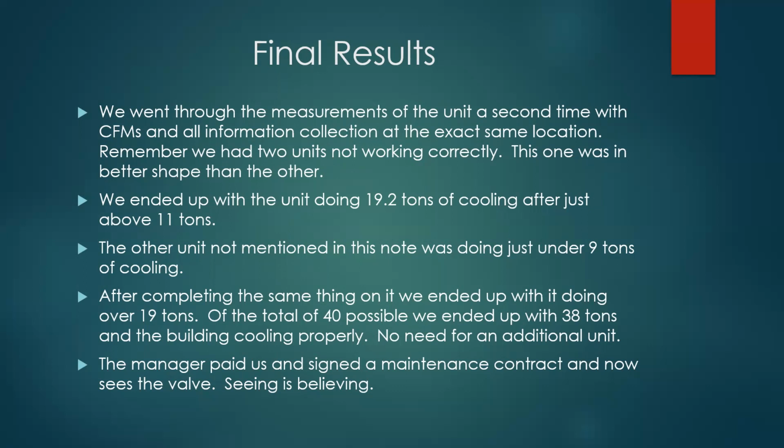We gained, you're not going to get to 100%. There's weakness in there. We considered this to be exceptional for what it was doing. The other unit was doing just under 9 tons. We ended up bringing it up to right about 19 tons. After completing the same thing on it, we ended up doing a little over 19 tons. Of the total 40 tons possible, we ended up with 38 tons of cooling, and the building was comfortable.